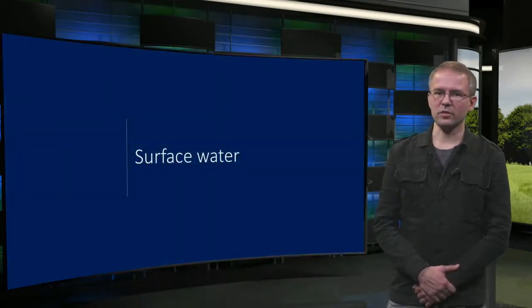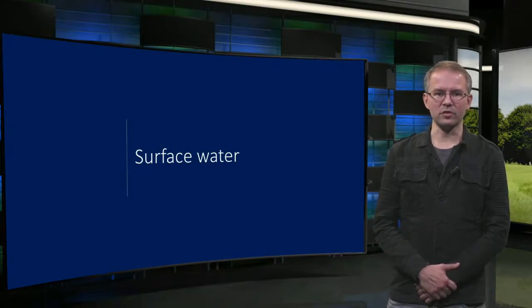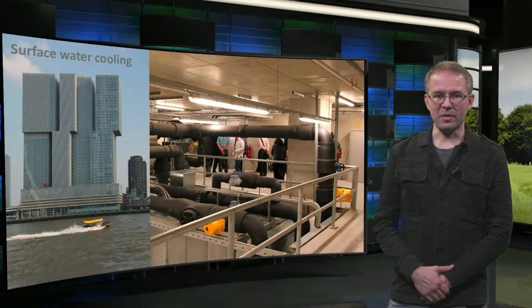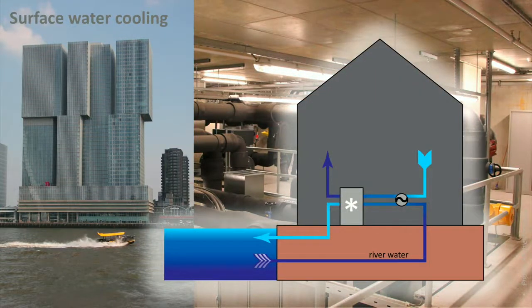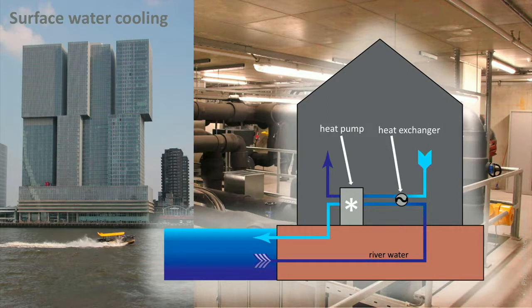The second source is surface water. Lakes, rivers, and the sea can all be used for heating or cooling. An example that combines several technologies is the Rotterdam building, which uses the Maas river for cooling. Here, river water is pumped through the cooling plant in the building and either used with just a heat exchanger or, if needed, cooled down further with a heat pump. The same principle can be used for heating — for example with seawater, which is relatively warm in winter — however, a heat pump is then necessary.